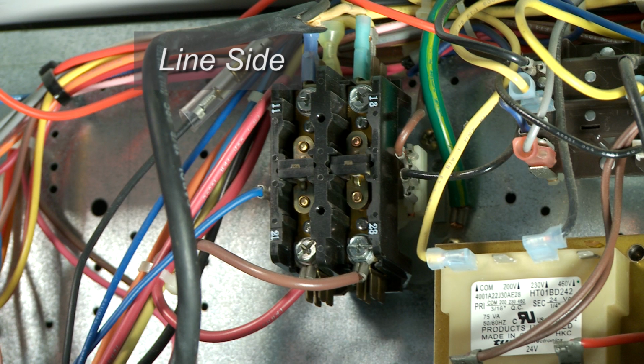To complete the power connection to the transformer, connect one end of the included 16-gauge wire to the line side of either the main contactor or compressor in the unit. Care must be taken during this step to ensure the transformer is connected to the side of the contactor that is always hot. The controller needs a constant source of power. Connecting it to the load side will result in a non-functional installation.